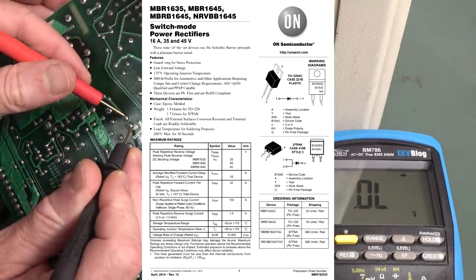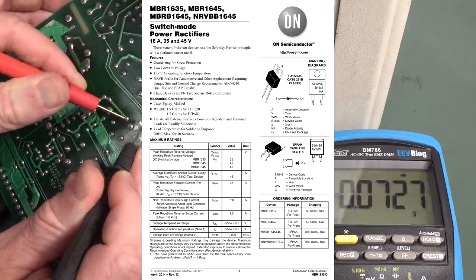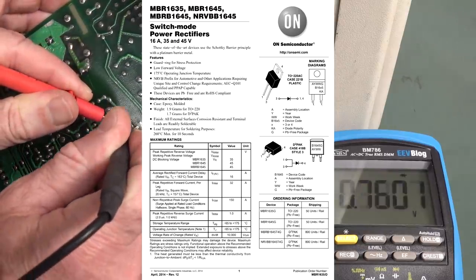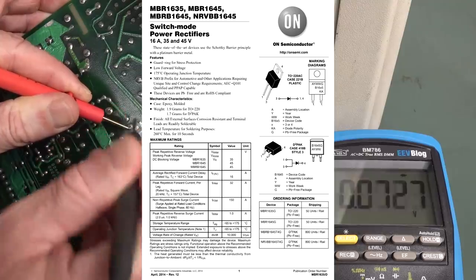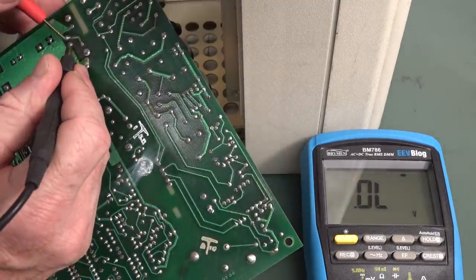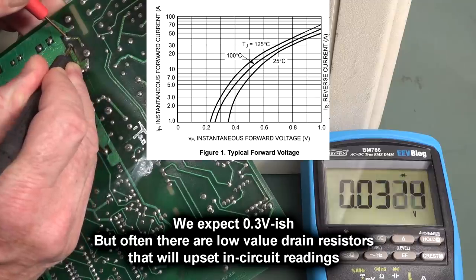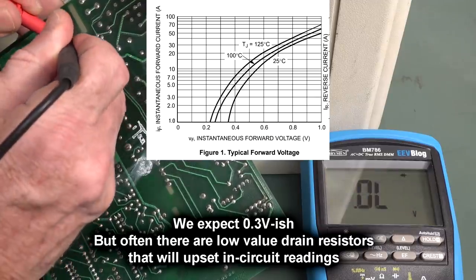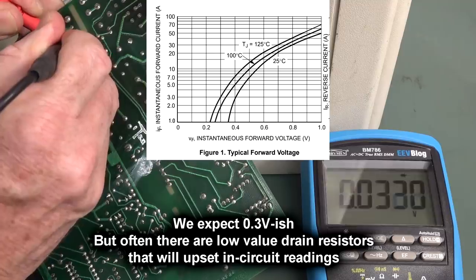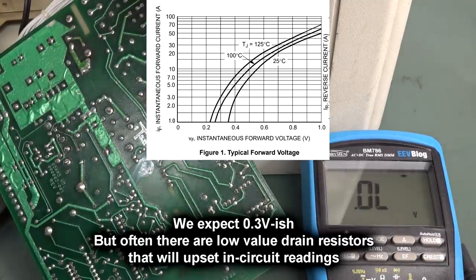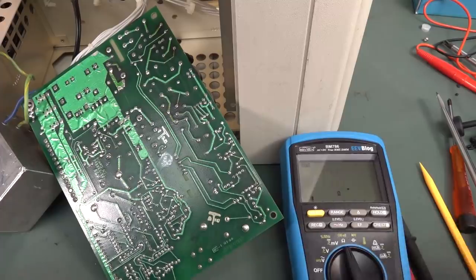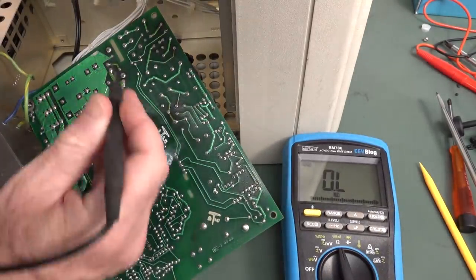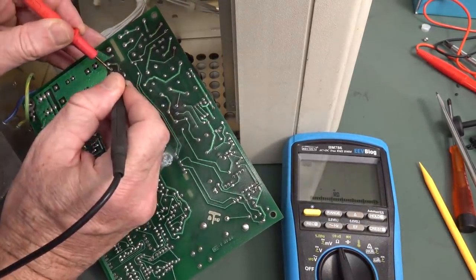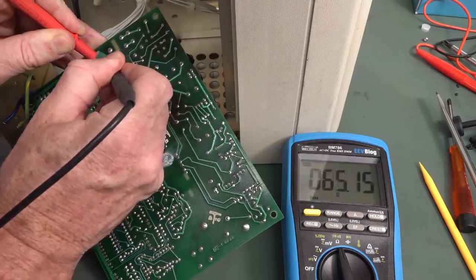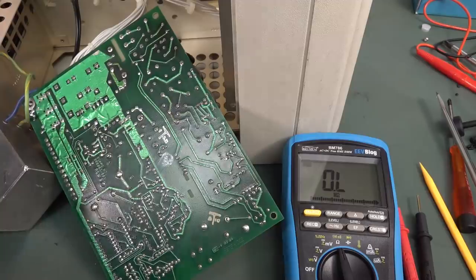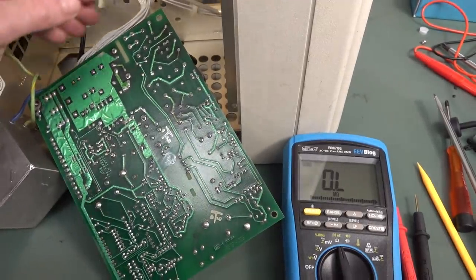The one over here is here, so 0.07 volts, 0.072, well, that could be low in-circuit impedance, 0.03, okay, that may be low in-circuit impedance. We can go over and measure our ohms, but I suspect, so yeah, 67 one way. Yep, so they're not shorted, but that doesn't indicate that they're a dead short.